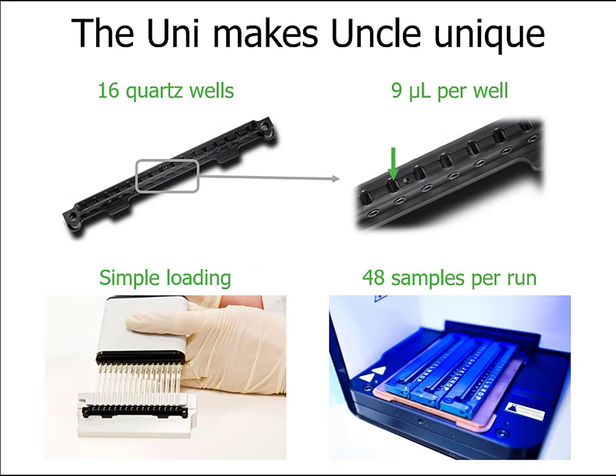Allow me to introduce one of the key features of the UNCLE: the UNI sample holder. The UNI is composed of an array of 16 quartz cuvettes that are easily loaded with a pipette. The high-grade quartz gets us great optical sensitivity for fluorescence and light scattering data, and the frame is anodized aluminum that provides efficient heat transfer. The 16 samples are loaded into the UNI and then sealed in a blue frame with a silicone seal, so evaporation won't be a problem during a heat ramp.